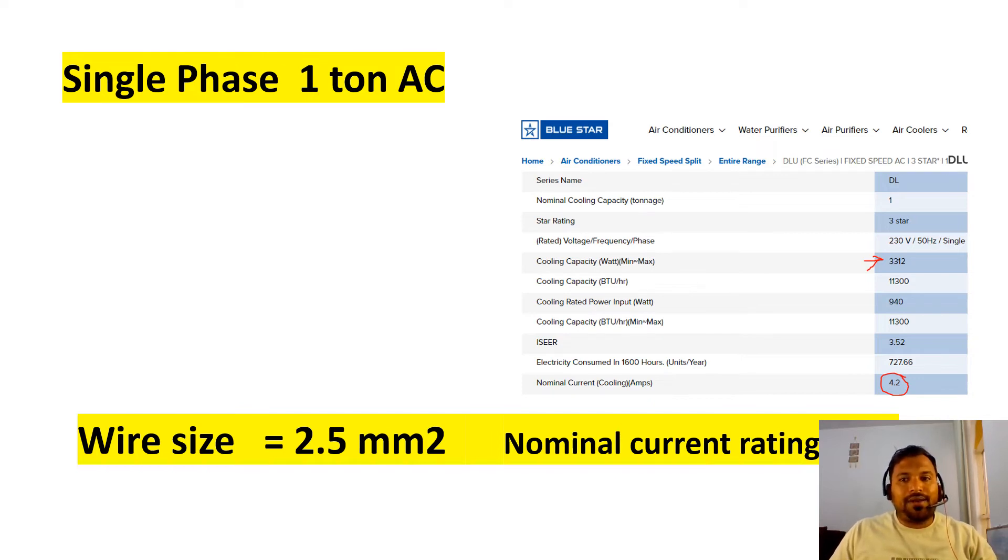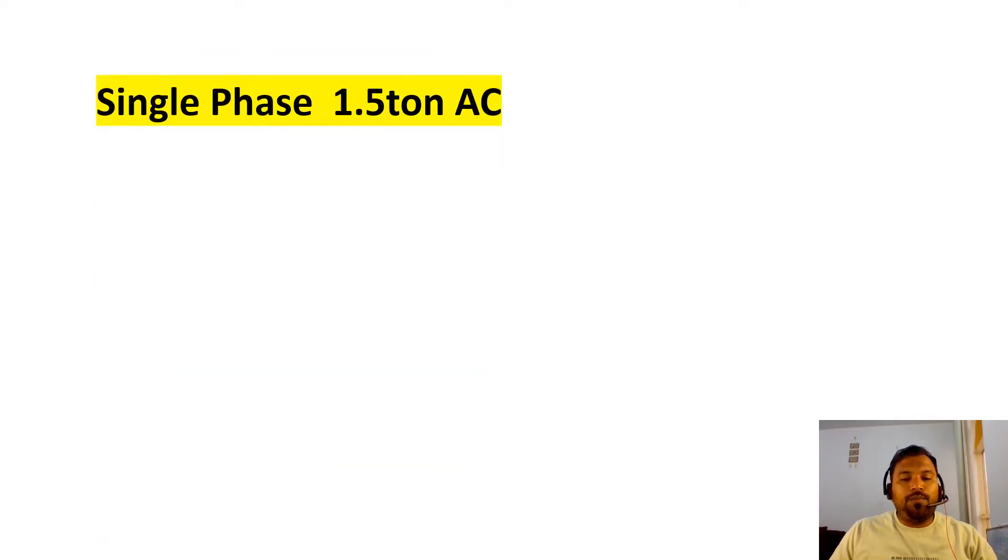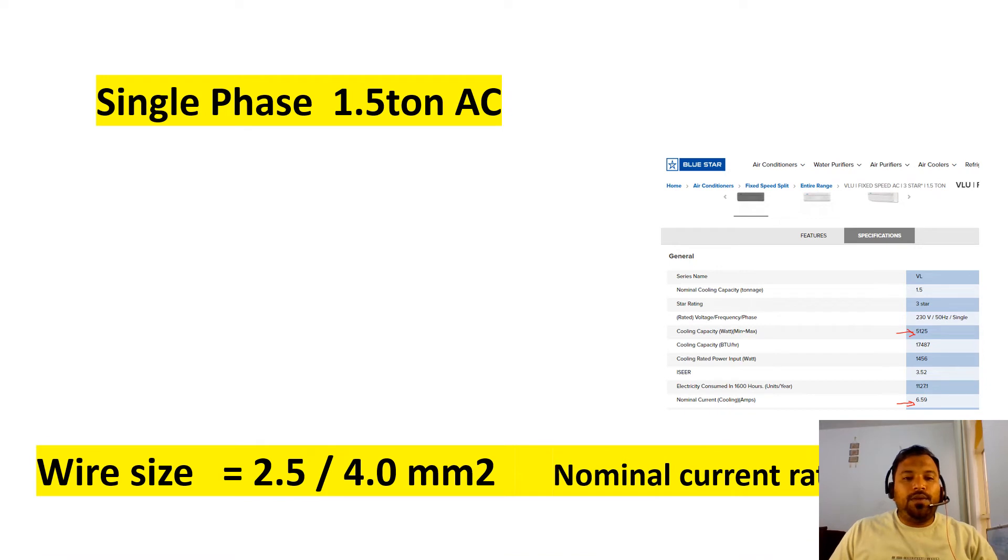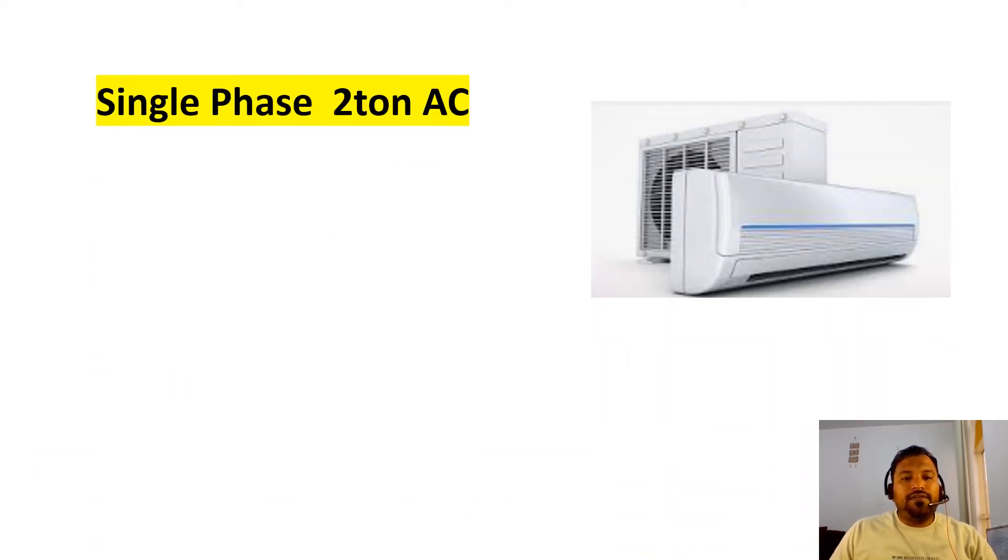Now let's see the next. 1.5 ton AC. 1.5 ton AC will be recommended 2.5 or 4 mm square. My recommendation, you will go with the 4 mm square.